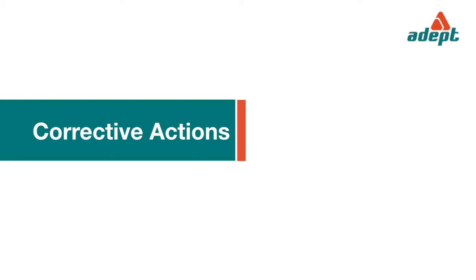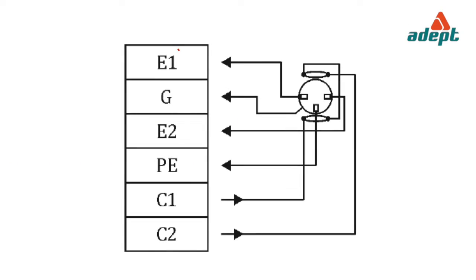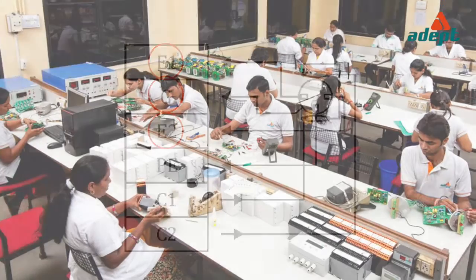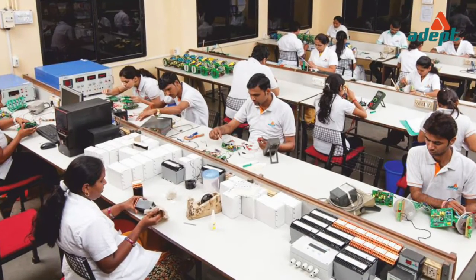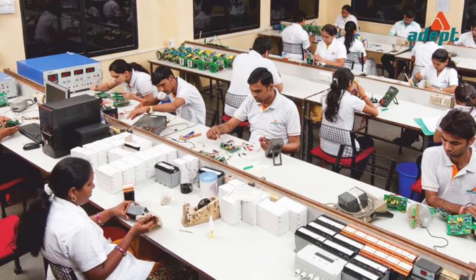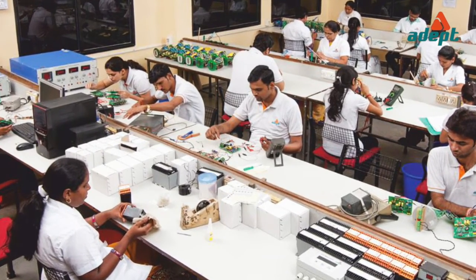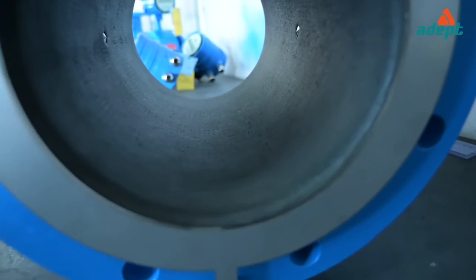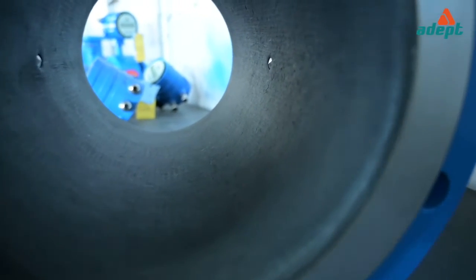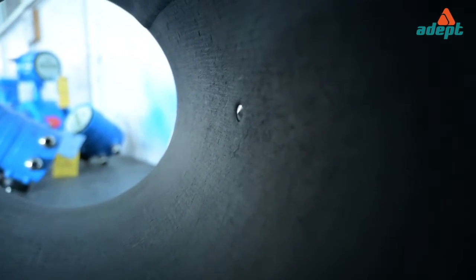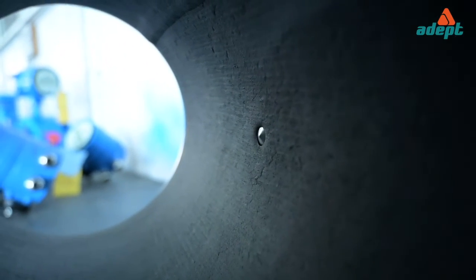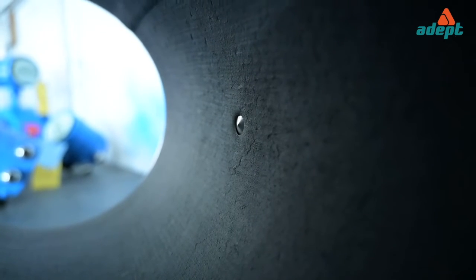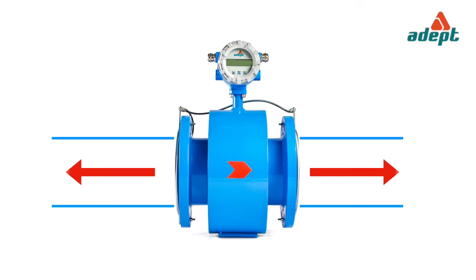Corrective actions: disconnect E1, E2, and G at the transmitter and short them together. If the indication is still non-zero, send the transmitter to the factory. Otherwise, isolate and remove the flow tube, remove any deposit on and around the electrodes and check.